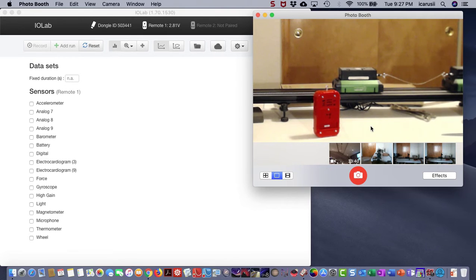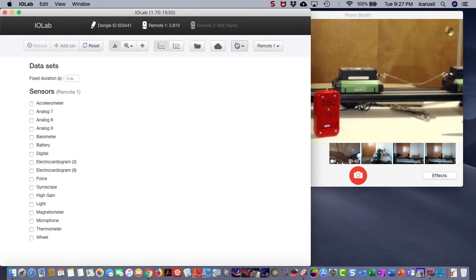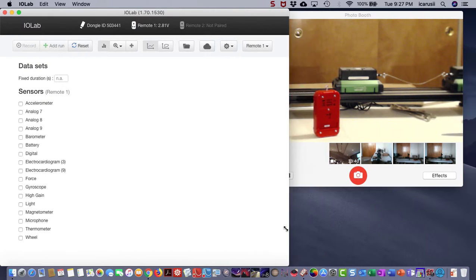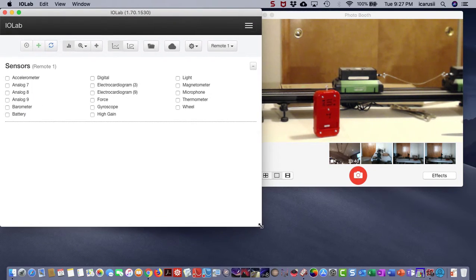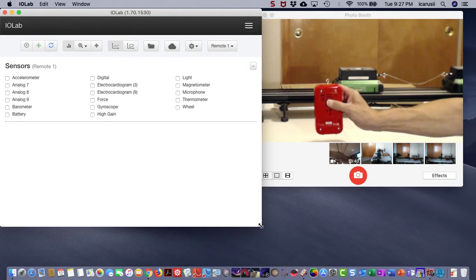So here's my IO device, and as you can see, I have it on a level surface, and I have the dongle into the USB drive, and what I'm going to do is calibrate the device for the force sensor. Now that's going to be important. What you're going to need is the IO device. You put the eye bolt in. Be careful how far you screw that in because you can damage the force sensor if you screw it in too hard, but just enough, about like this.